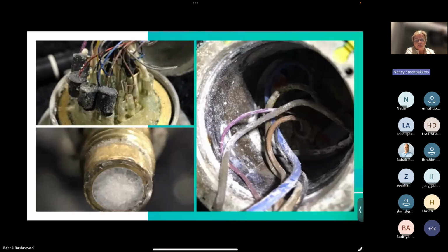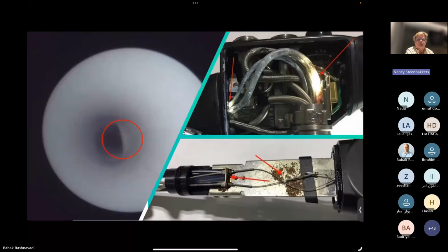There are all kind of little pictures that I put in this information. Here on the left side, you still see there is a stent in the channel. And I heard now that some manufacturers of leak pumps or pre-cleaning are mentioning you can clean it just with the pump with water and air, and there is no need to use any detergent anymore, and brushing is not mandatory. But I can assure you, a stent in a channel, if you're not brushing it in a good way, your stent will stay there. So with the next patient, when you're doing a biopsy and you go with the needle through the biopsy channel, this patient will get this stent in his body. I think you don't want to have these kind of situations in your own endoscopy department.